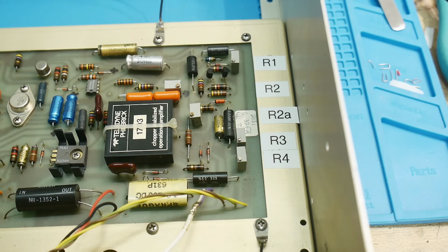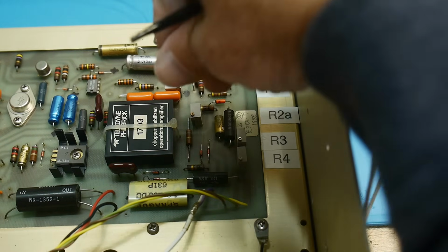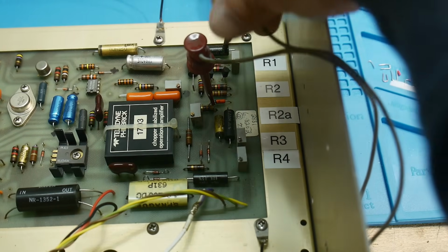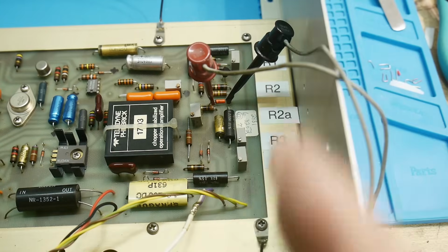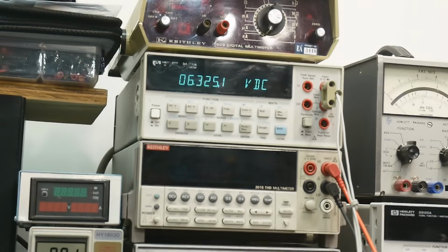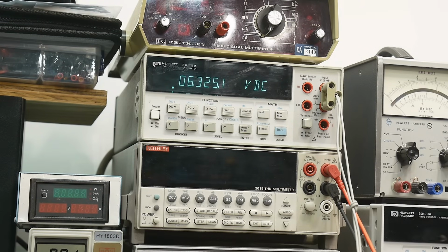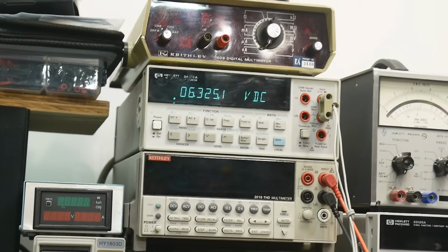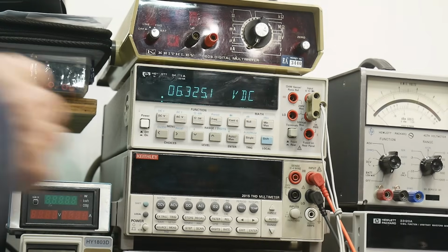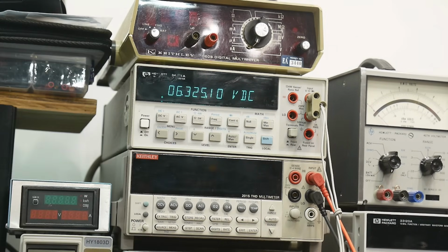All right, so let's go ahead and put a voltmeter on that Zener diode, okay? Let's see what it's operating at right now. It should be 6.3252, and it's at 6.3251, okay? So let's make my voltmeter a little more sensitive. I'll put it on 6 and a half digit resolution, and then we will take a tool and adjust what's known as R1.